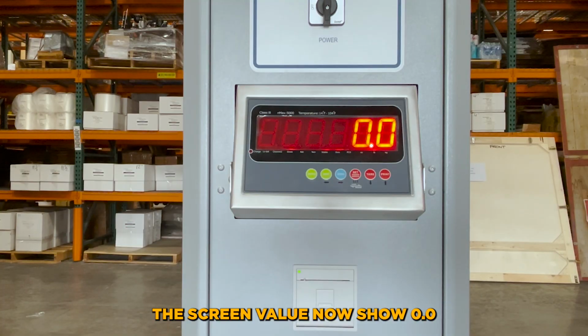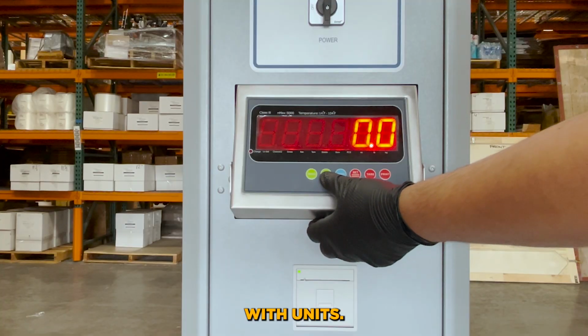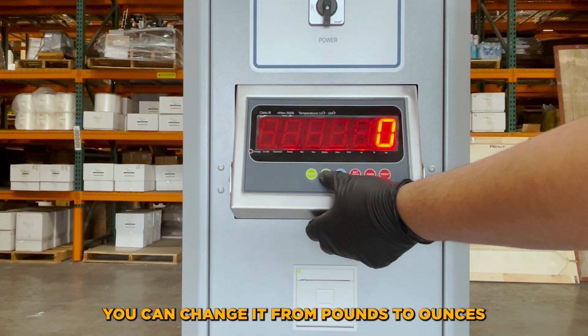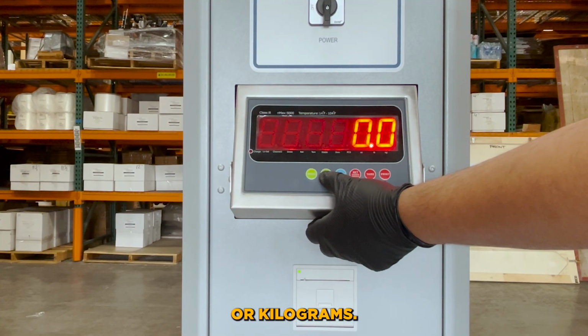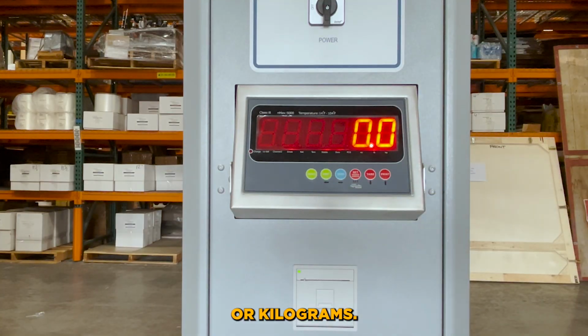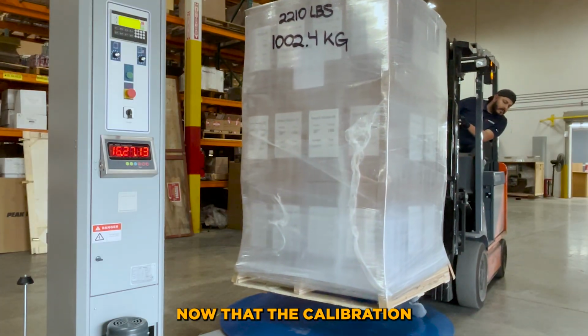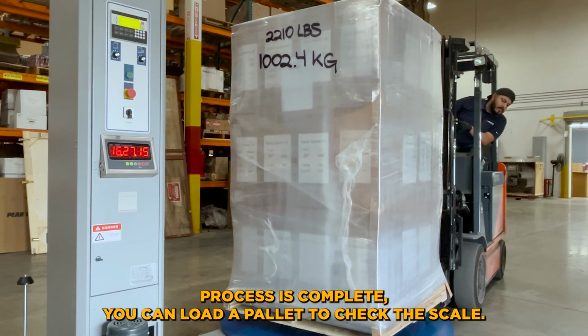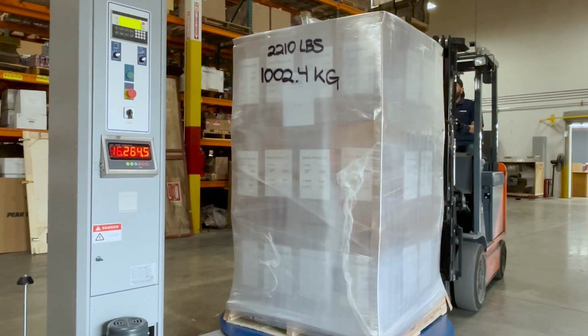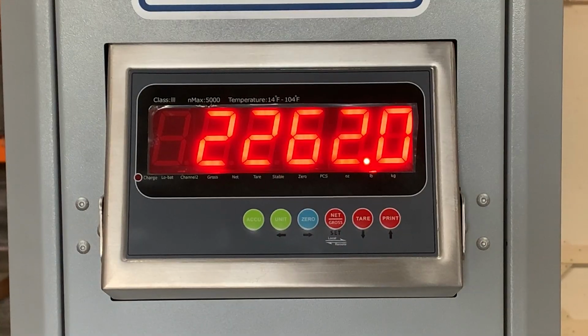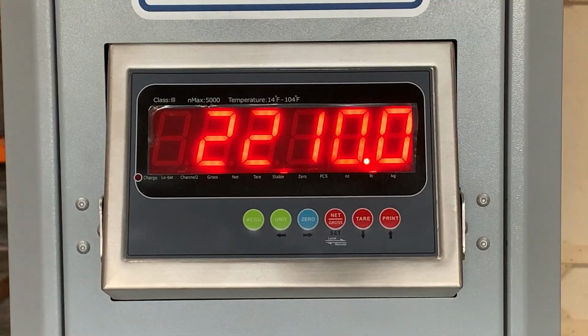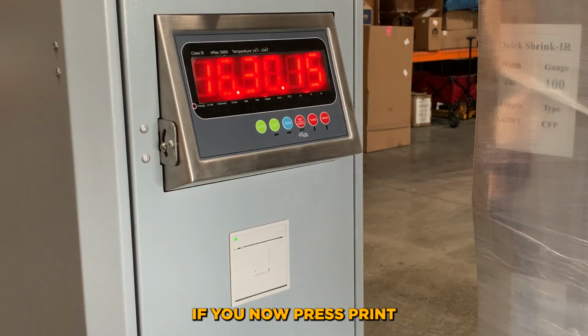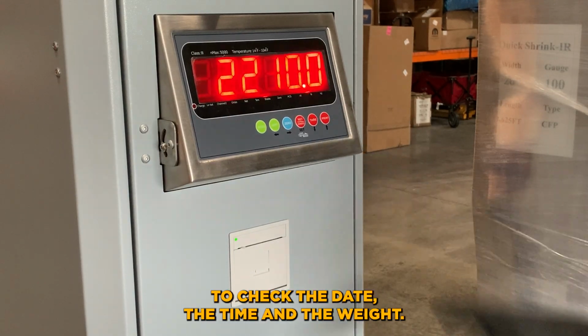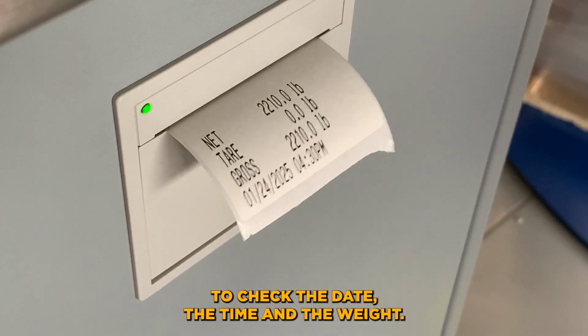The screen value now shows 0.0. With units, you can change it from pounds to ounces or kilograms. Now that the calibration process is complete, you can load a pallet to check the scale. You can now press print to check the date, the time, and the weight.